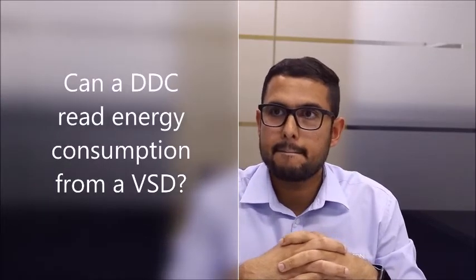So what it needs to do is, not all the systems are operating all the time. We need to be careful on that. There needs to be a certain set of calculations that needs to happen. That means the BMS will look at the fan statuses or equipment statuses, and it will calculate a demand based on the flow rates and the valve sizes. And then based on the demand, it will modulate the pump speed up or down. So if we have a variable speed drive installed on a pump, yeah.